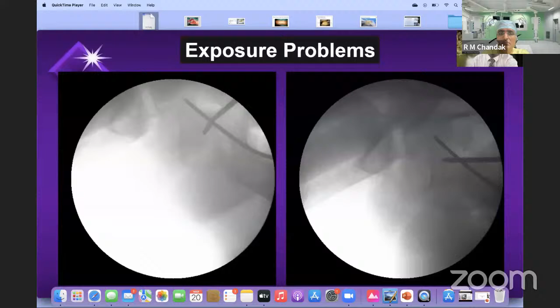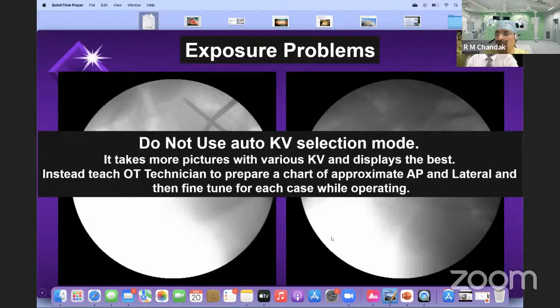Then there is some problems. Don't use the auto KV selection mode, because it takes images at different KV, like 70 KV, 72 KV, 74 KV. Then if the body requires 100 KV, then lastly it goes to 100 KV and displays the image. So unnecessarily the body gets exposed to many KV before the final one is taken. So normally what I do is I just keep it at auto mode and take a picture, and I see the readings of the C-arm. If it says 100 KV, then I make it into manual mode and keep it at 100 KV and take the next picture. So with one single shoot you can take without the problem of exposure. So never use the auto mode without knowing how it works.